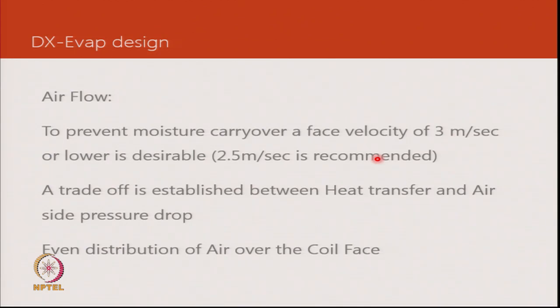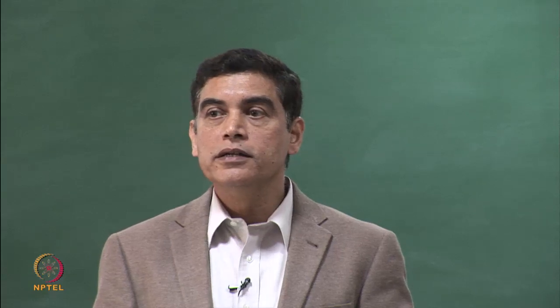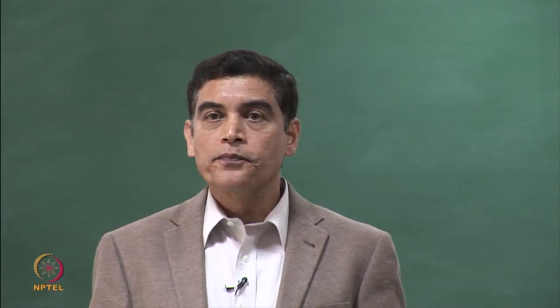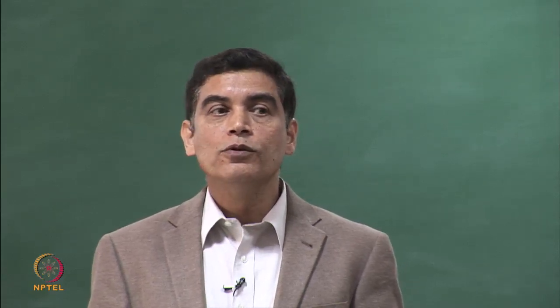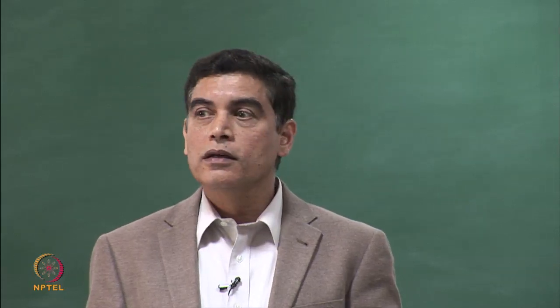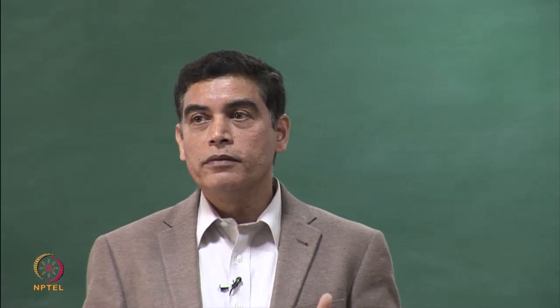Another aspect to look at is the air distribution over the coil face. When designing the air flow path, air enters the air conditioner through some opening and a blower draws air over the coil, so we need to space components in a way that there is uniform air distribution.